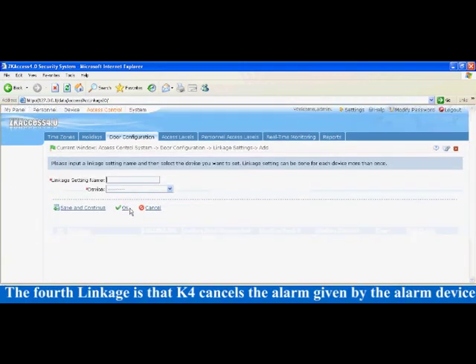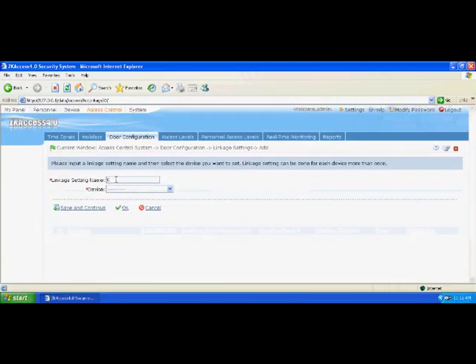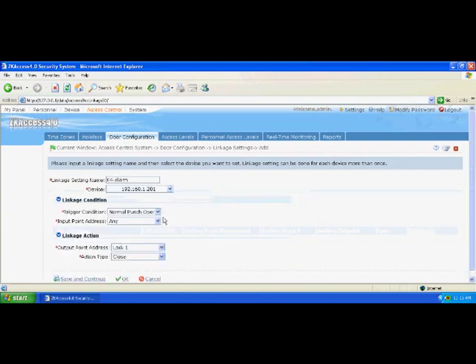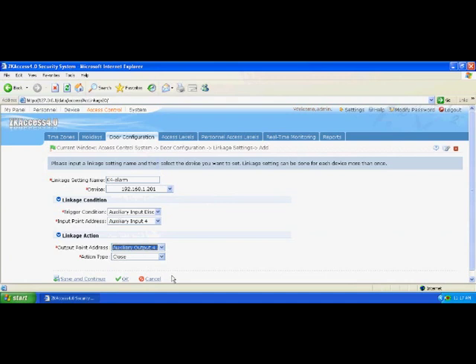The fourth linkage is that K4 cancels the alarm given by the alarm device. The trigger condition is set to auxiliary input disconnect, the input address is auxiliary input 4, the output address is auxiliary output 4, and the action type is close.